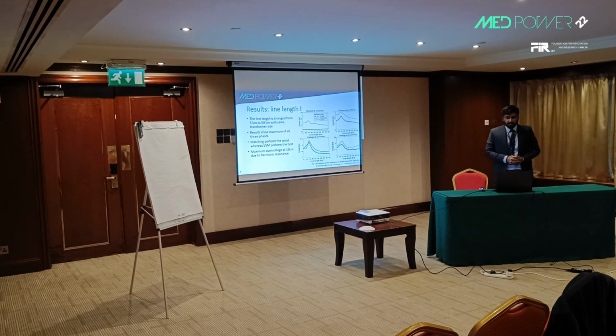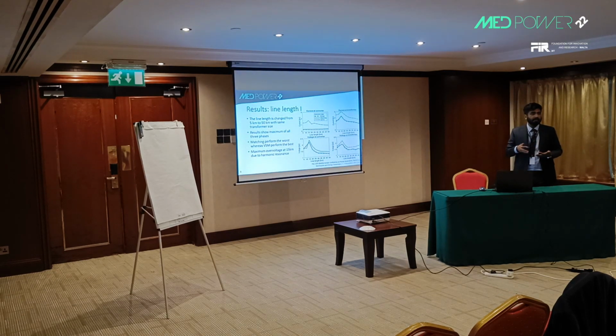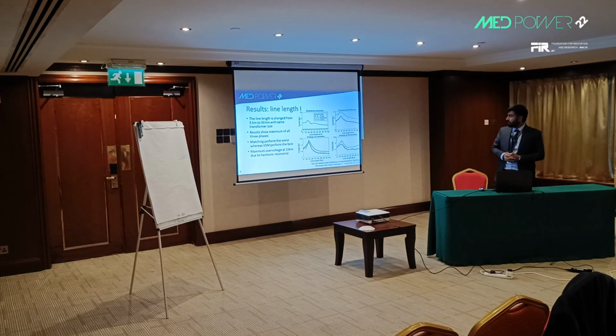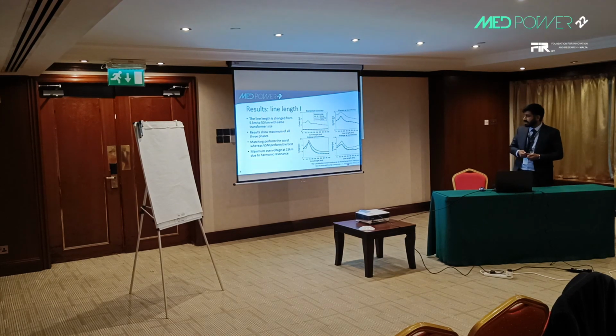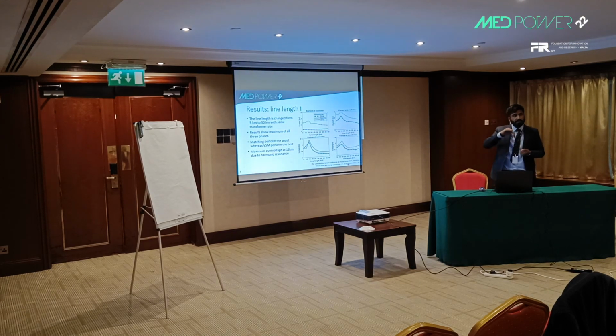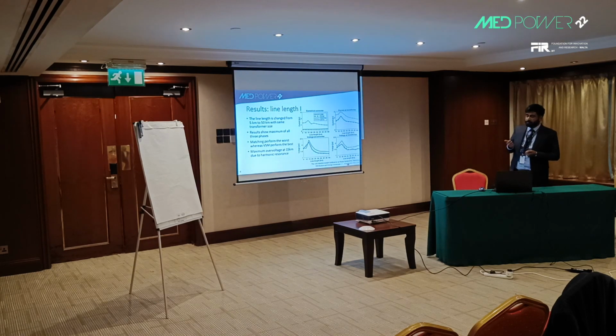In the next step, we changed the line length from 5 kilometers to 50 kilometers in order to see how the line interaction, line changes, can have an effect. And what we saw is that all of the converters have similar trends. The voltage at the transformer started to rise, and at 15 kilometers it has its peak, and after that it starts to decrease. And 50 kilometers is where the harmonic voltages are at maximum, and I will show in the next slide why.